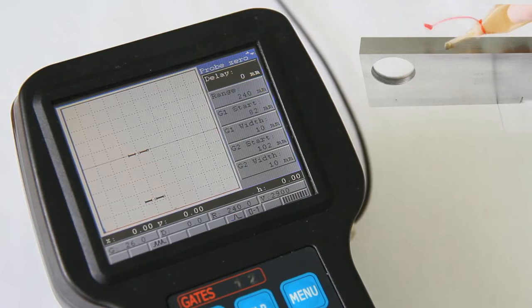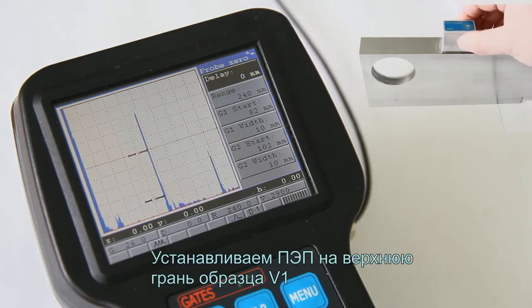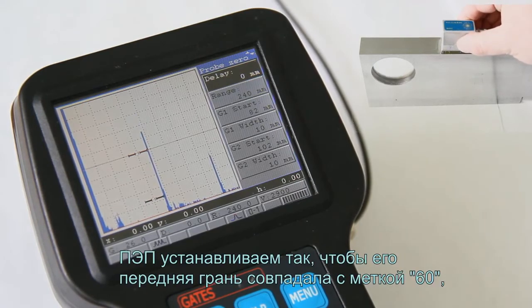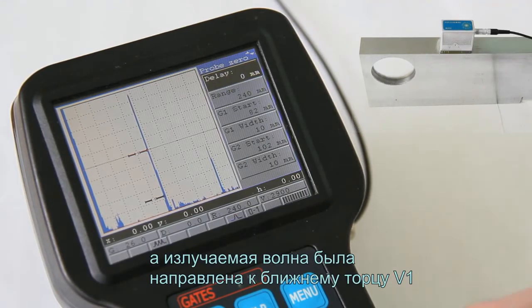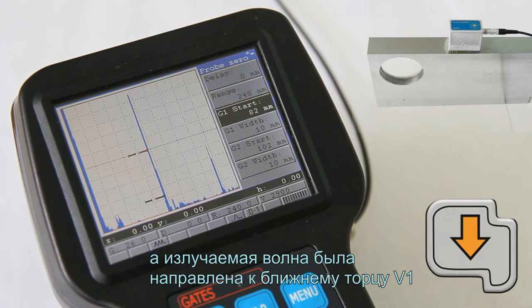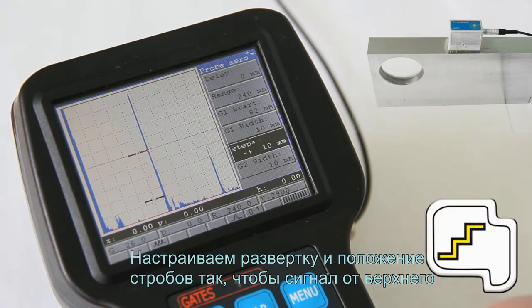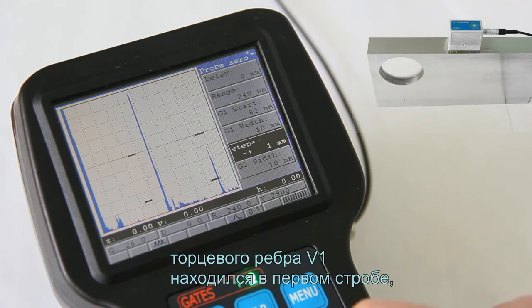Place the probe at the upper edge of V1 block so that the front probe edge coincides with 60 mark and the generating wave to be directed to the nearest butt end of V1 block. Adjust the scanned gate so that the signal from the upper end edge of V1 to be in the first gate and that from the lower edge of the same end in the second gate.